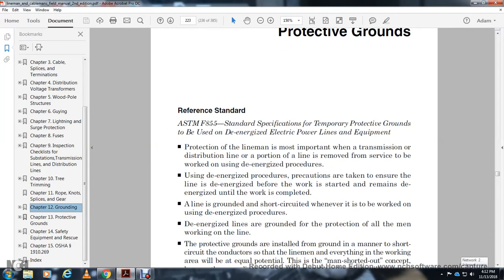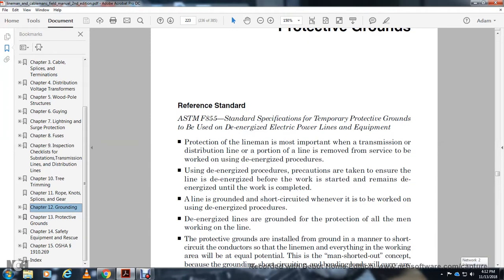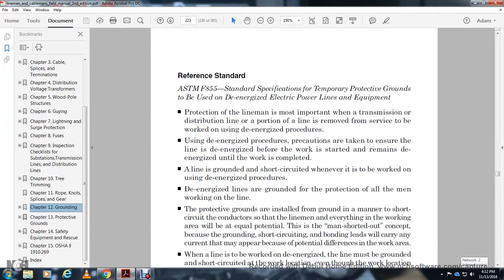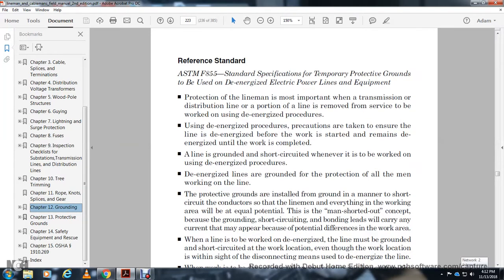Protective grounds are installed on the line in a manner that short-circuits the conductors, so that the linemen and everything in the working area will be at an equal potential. This is the man shorted out concept. Think of the grounding and short-circuiting bonding leads as carrying any current that may appear with potential differences in the work area.